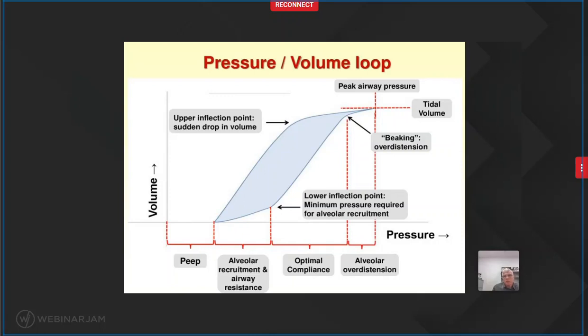So ideally, you want to terminate your breath right here. You don't want to go beyond that. This part here is the peak inspiratory pressure. And this right here is the tidal volume achieved with that breath. So this is the inspiratory limb, and this is the expiratory limb of that pressure volume loop.